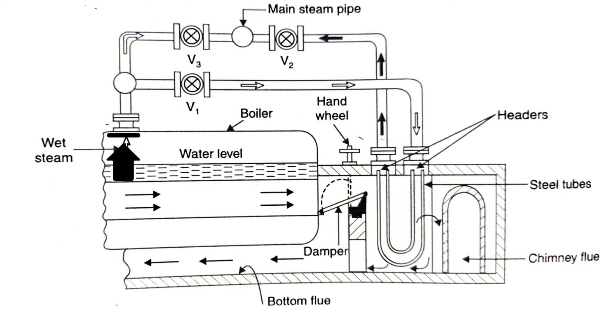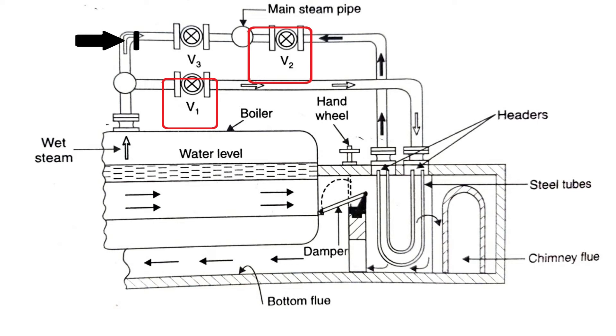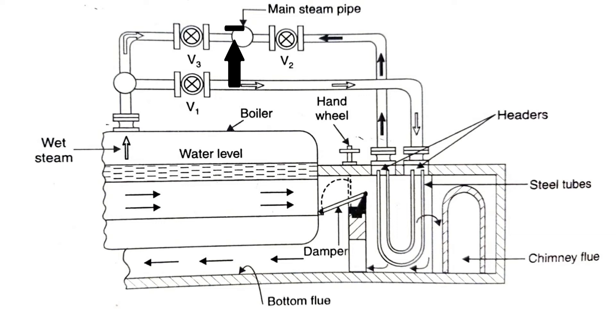Now we will discuss the working principle of the superheater. Steam from the boiler enters and leaves the headers as shown by the arrows, also showing how the steam pipes may be arranged to pass the steam through the superheater or directly to the main steam pipe. When the steam is taken from the boiler directly to the main steam pipe, valves V1 and V2 are closed and V3 is open — so at that time steam is directly supplied to the turbine without passing through the superheater.